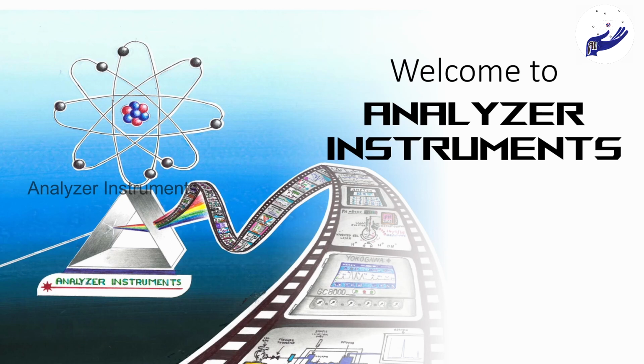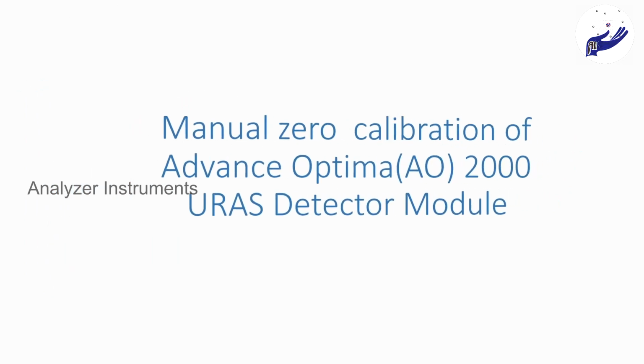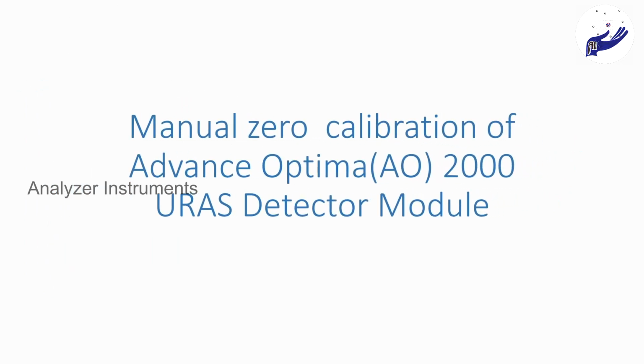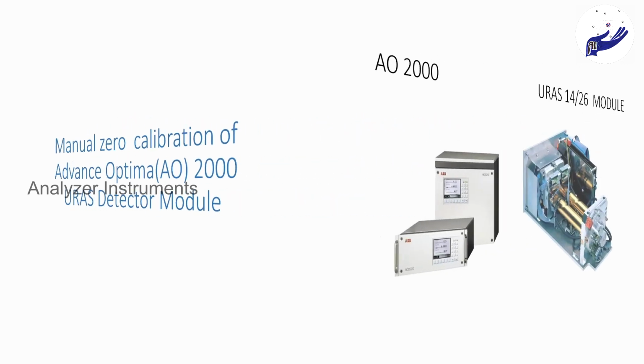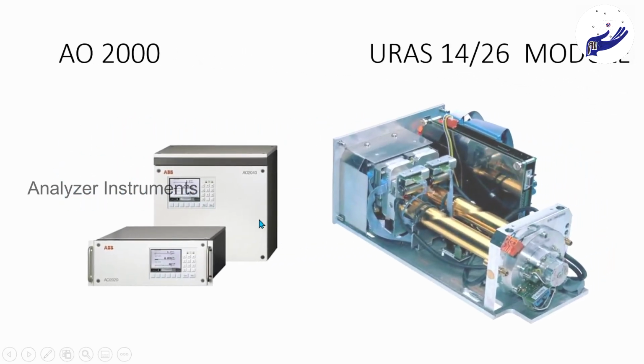In this video, we are going to check how to do manual calibration for the ABB Advanced Optima AO2000 model. This is the rack mount analyzer and this is the wall mount model. This is the URAS 14 model which we are using here, and this calibration procedure will vary from the original calibration procedure in the manual. Kindly refer to the user manual for more information on calibration and working procedure.